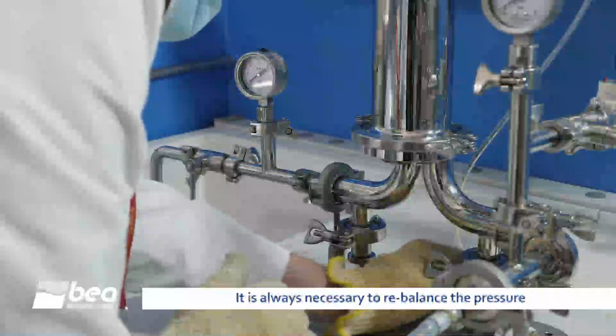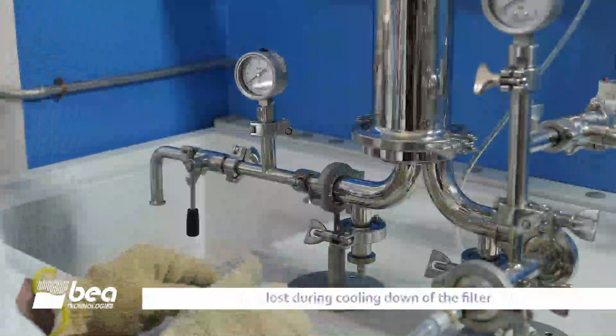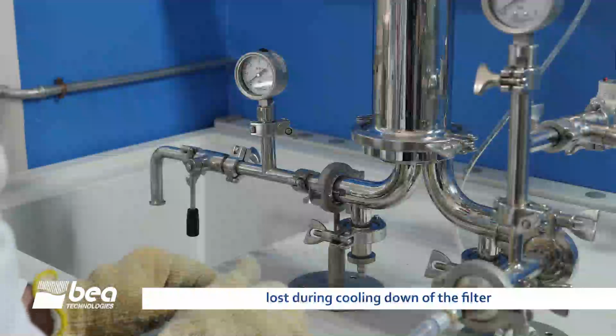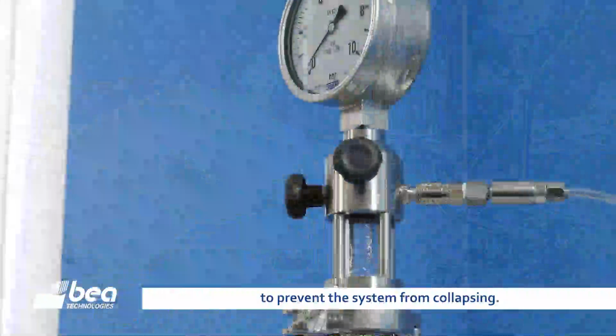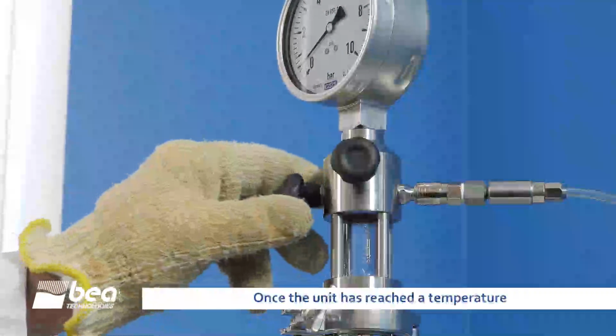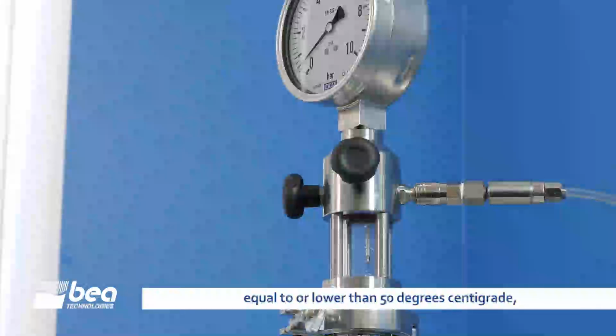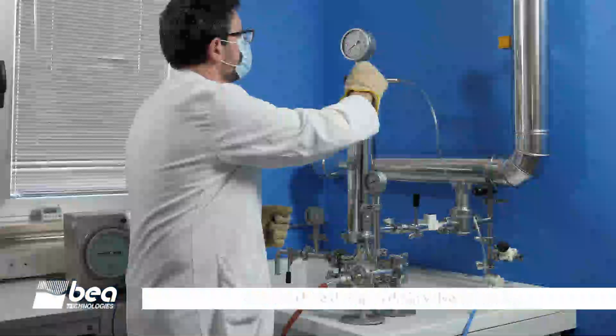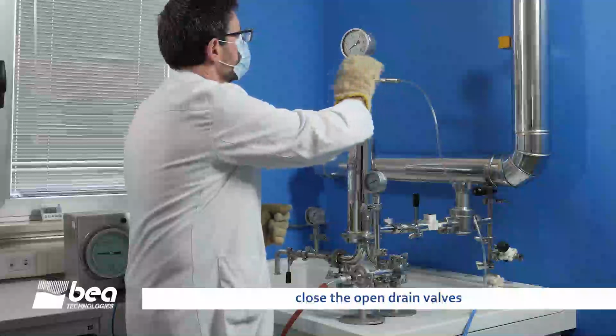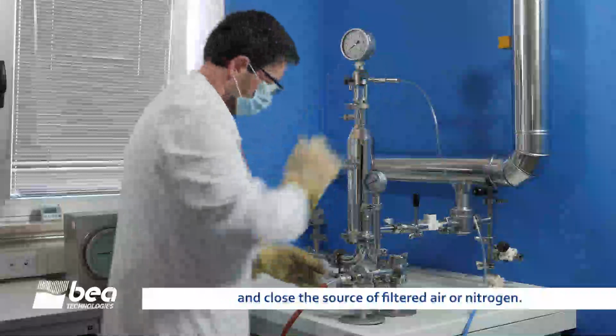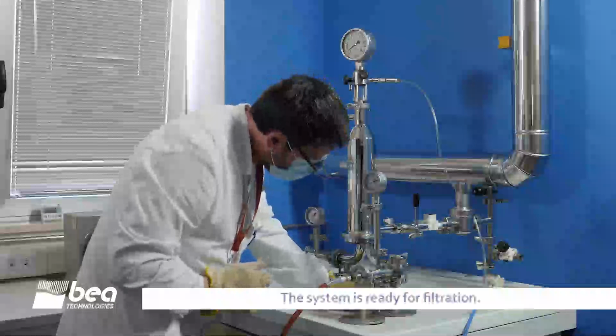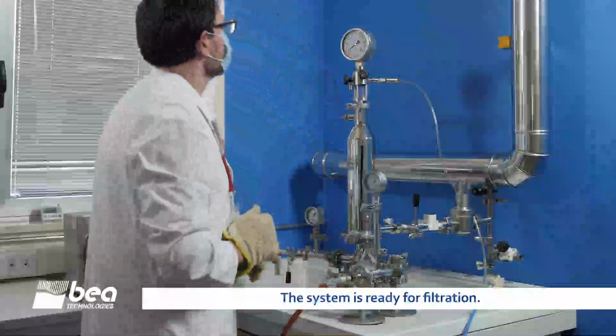It is always necessary to rebalance the pressure lost during the cooling down of the filter to prevent the system from collapsing. Once the unit has reached a temperature equal to or lower than 50 degrees centigrade, close the open drain valves and close the source of filtered air or nitrogen. The system is ready for filtration.